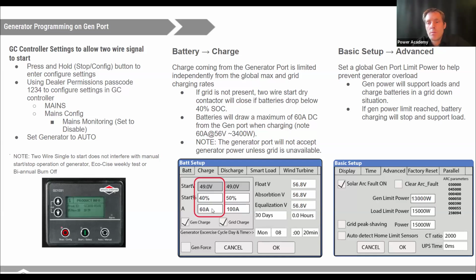If you have one of our 13K generators, you don't want to try to charge your batteries at 12 kilowatts, because that would only leave 1 kilowatt of power left over to cover the loads in the house. So if you do have a 13K generator, come over here to the basic setup tab. Under basic setup and then advanced, you can limit the generator power. What this will do is reduce the charging rate so that you don't overload your generator.